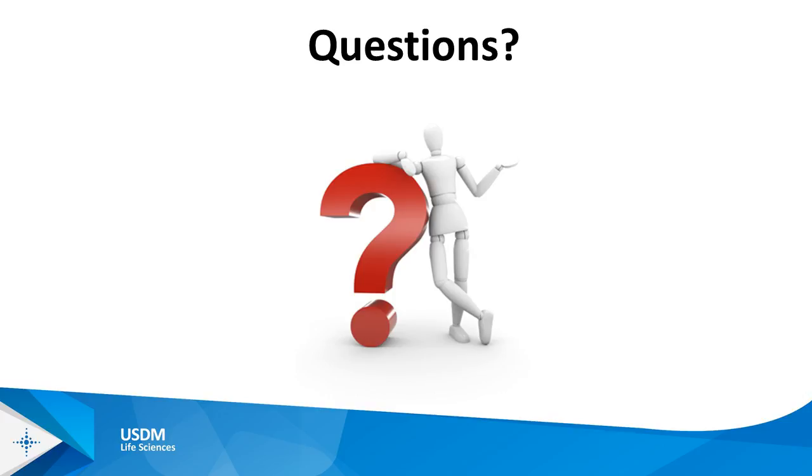Great question. Thank you, Becky. No, it doesn't. As I mentioned earlier on, it really only applies to the label requirement. So importantly, and I think this is critical, if you haven't started to understand your master data management program and how you're going to collect, store, normalize, validate, and finally submit data to the GUDID, those requirements still exist for the FDA's devices. So for September 24th of 2015, you still need to get all of the information into the GUDID for your products, even in advance of them being, if you will, marked or identified with the UDI.